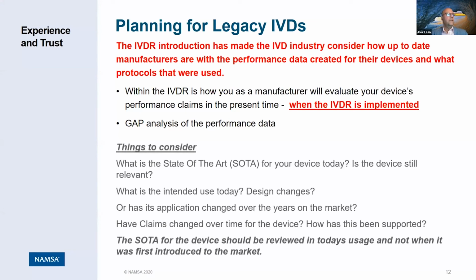Things to consider: what is the current state of the art? State of the art is not what it was 20 years ago. What is the intended use today? What can you expect? Are there any design changes that come up that you still want to do under the directive or under the IVDR? Have claims changed over time, in the intended use, instructions for use, or in the labeling? How is that now supported? Perhaps you need to limit claims because you don't have the evidence. The state of the art of the device should be reviewed in today's usage and not when it was first introduced into the market. So you better do a determination of that.